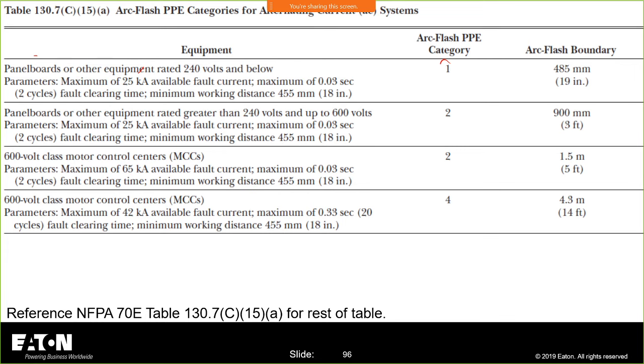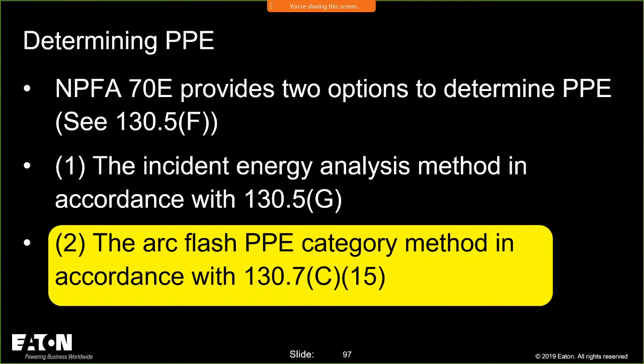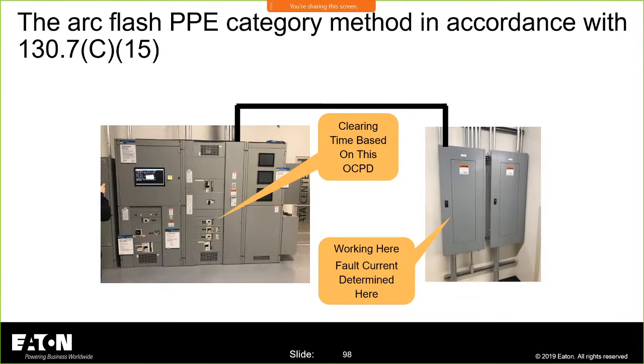Now, I could probably come up with scenarios to show, well, look, your incident energy is more than that, because the arcing current is so low. But to Jim's point, I need to get people into PPE. That is our biggest chore. So the arc flash PPE category and method is determined in 130.7(C)(15). I have the same picture.